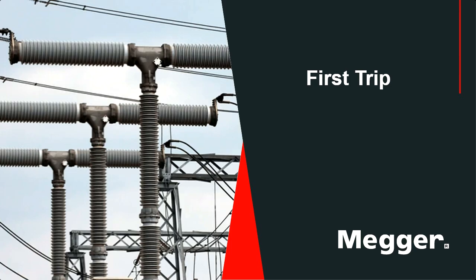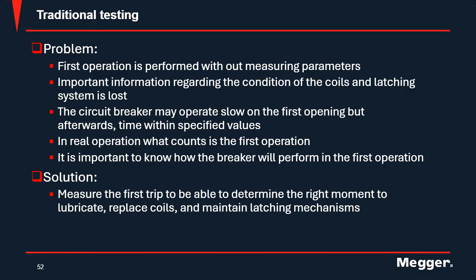All right. Now that we've talked about all those, I want to talk about something called first trip. So like I said at the beginning, circuit breakers will generally sit idle in the closed position for months or even years without being operated. And in that time, the linkage, the grease, everything inside that operating mechanism becomes stiff and slow. The problem is that first operation usually goes without any measurement parameters, so people don't usually monitor it. There is important information regarding the condition of your coil, your latching that is getting lost.